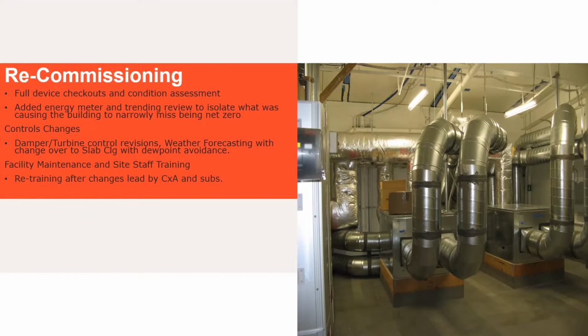So we did pre-flush the night before, depending on a low temperature threshold. Usually I think we started that if it was below 60 degrees at night, or it might have been like 62 or 64 or something like that. Start pre-cooling the building down, knowing that there was going to be a hot day. I think the limit on that was if it was planning to be a 78 or 80-degree day, we'd start pre-cooling the building down, especially if we weren't doing slab cooling. And then when slab cooling was going to be in play, we turned on that pre-cool for the entire evening.